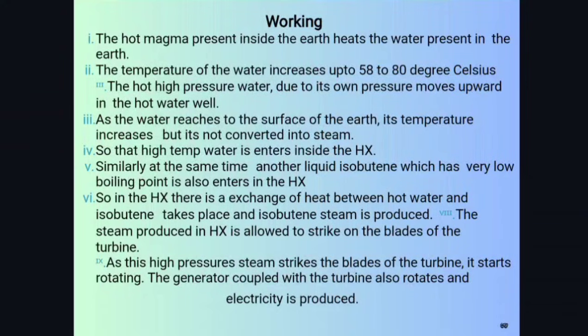Similarly, at the same time, another liquid, isobutane, which has a very low boiling point, also enters the heat exchanger. So in the heat exchanger, there is an exchange of heat between hot water and isobutane, and steam is produced. This steam produced in the heat exchanger is allowed to strike the blades of the turbine. As this high pressure steam strikes the blades of the turbine, it starts rotating. The generator coupled with the turbine also rotates and electricity is produced.